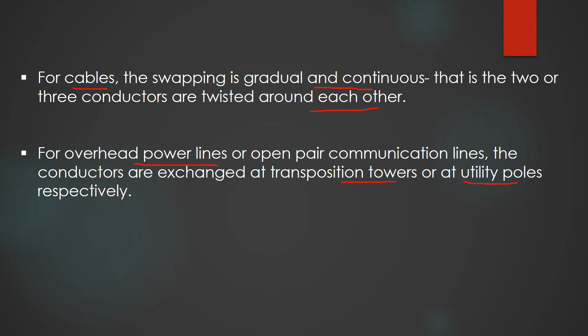Moving on to the need of transposition, that is, why transposition is necessary. The irregular spacing between the conductors gives a complex value of inductance, and thus it makes the study of the power system complex. The inductance of an unsymmetrical line causes voltage drop even if the voltage is in balanced condition. Because of this induced voltage, a magnetic field exists in the conductor, and this magnetic field causes interference in the line.